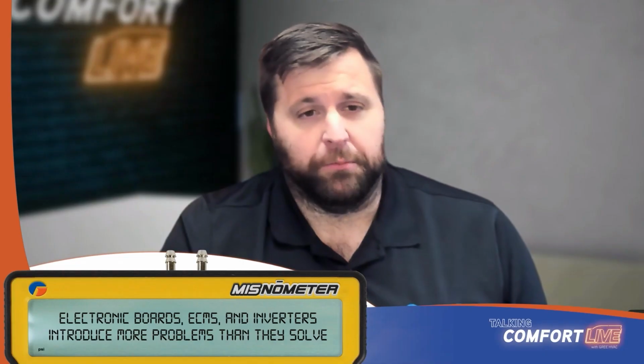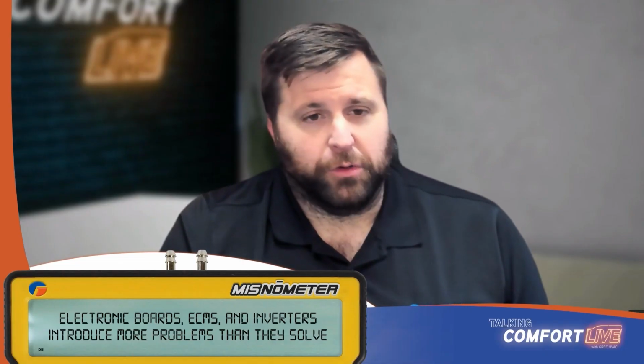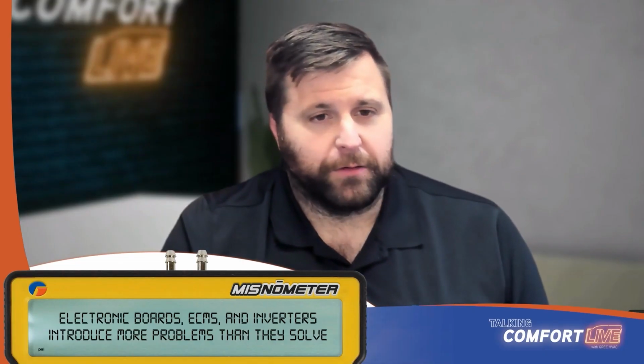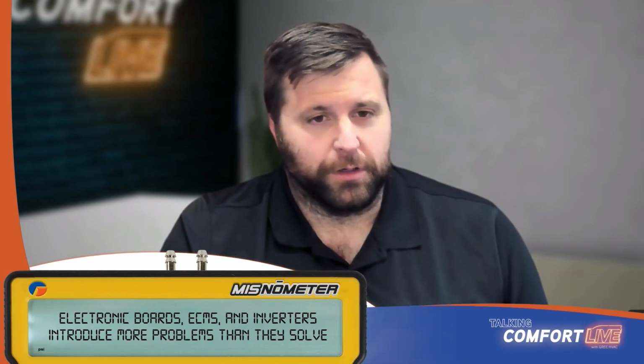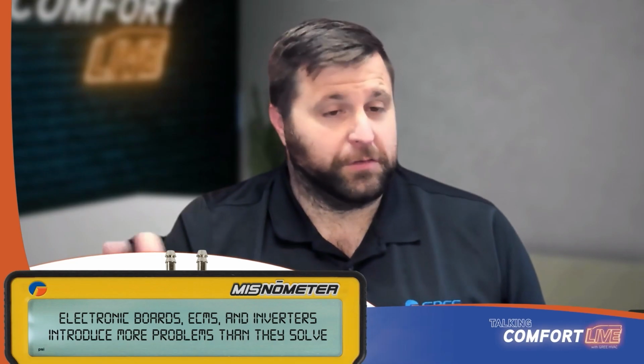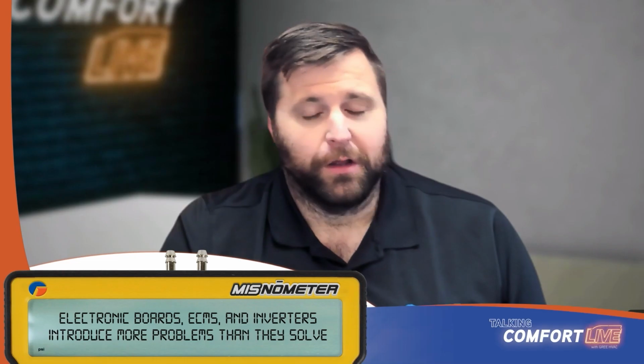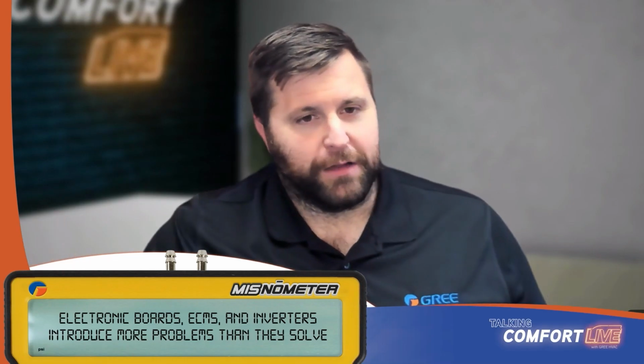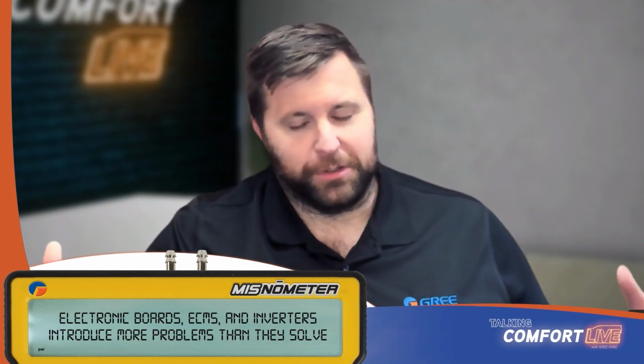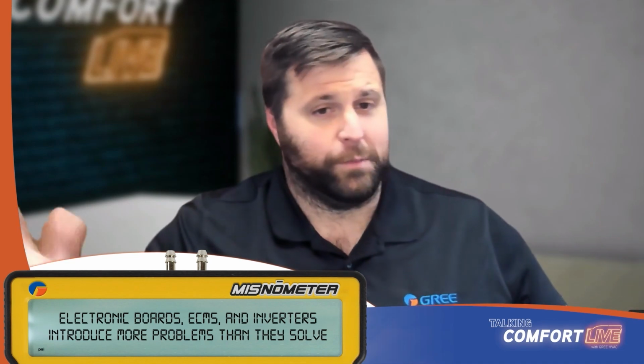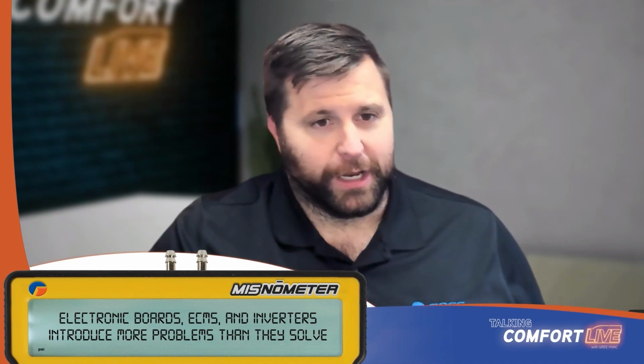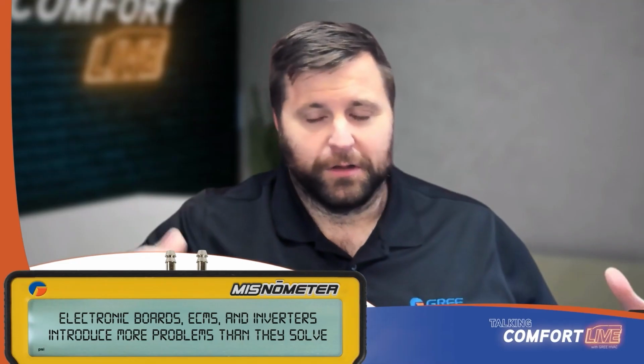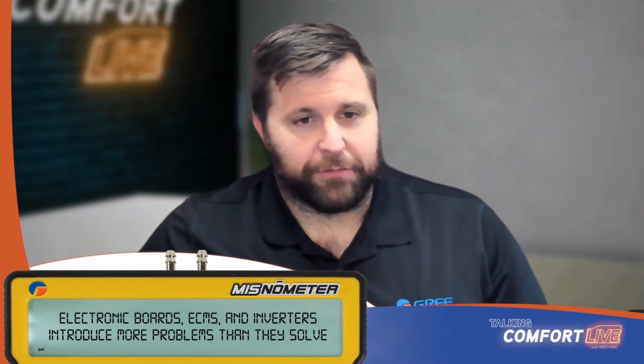All of our equipment has a way to monitor whether you might have a possibility of liquid coming back, or it's got freeze protection built into it. So unless you've installed something completely wrong, you're not going to end up with a solid block of ice in your compressor sitting there swimming in liquid, washing all the oil out of the compressor and all the rest of that, causing at least reduced life.